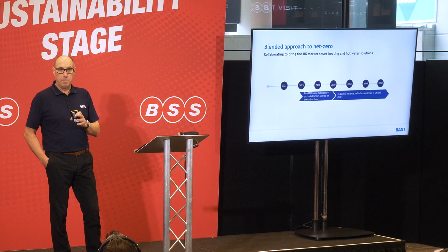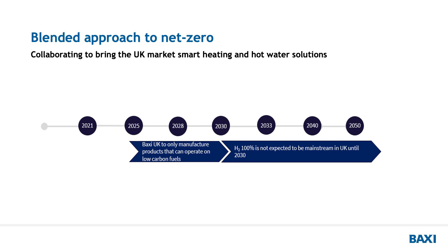A lot of the systems now aren't designed on 80-60 anymore. They're starting to come down to 70-50 and even 60-40, which then falls into the realms of the air source heat pumps. So as we move forward, 2030 onwards, BEIS are saying that they are going to start putting hydrogen into natural gas to reduce the carbon emissions. The UK, as it currently stands, I understand, have a Norwegian partnership arrangement with bulk hydrogen, which is the green hydrogen, and that is due to start coming in around 2030 to 2035. So we will see a change, but we're going to go on to the plant now that's being manufactured by companies like our own, where we're making the plant compatible with a certain portion of hydrogen.